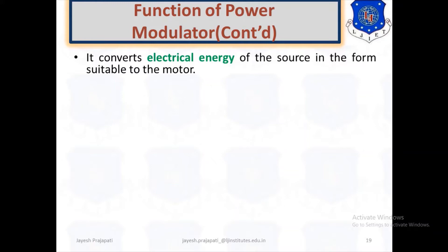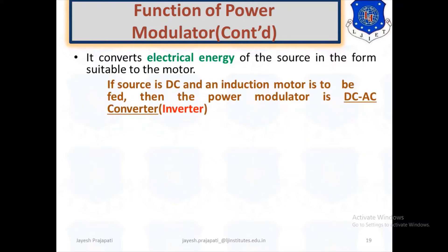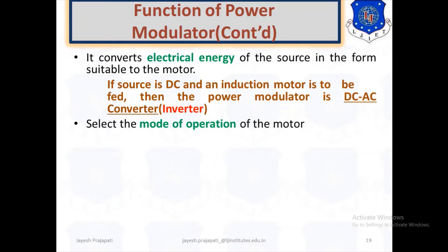The power modulator converts the electrical energy of the source into the form suitable for the motor. For example, if the source is DC and the motor is an induction motor (AC motor), the power modulator acts as a DC to AC converter, i.e., an inverter. It can also select the mode of operation of the motor, such as motoring or braking.